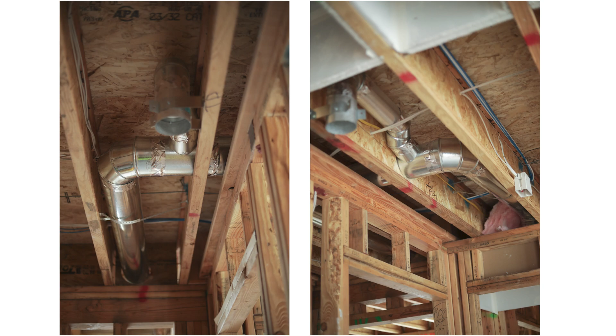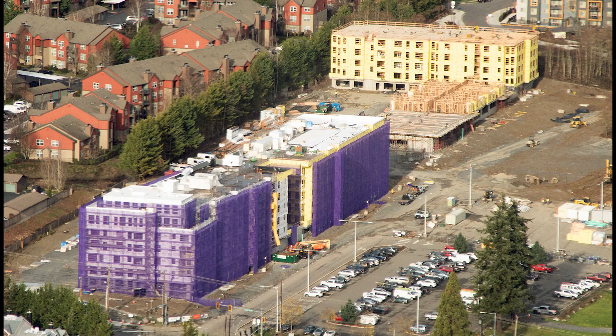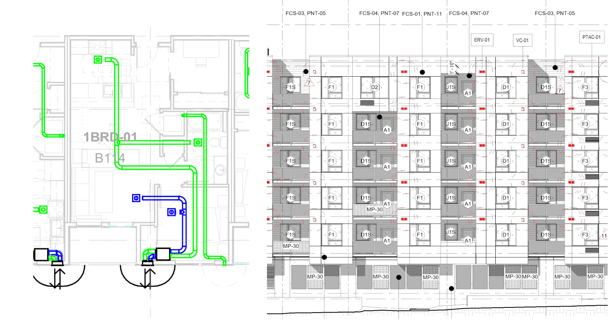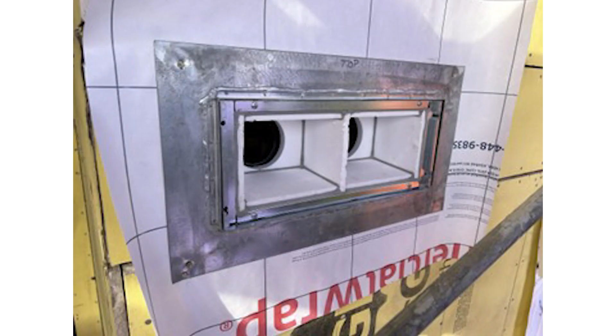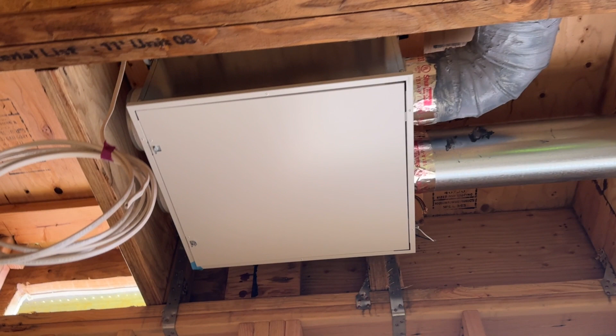Once routing was determined by the structural and mechanical engineers via rigorous coordination, the architect had to verify the clearances required by code for the ERV inlet and outlet were met at the exterior of the building. A new combination ERV exhaust termination and intake on the market was used, helping alleviate some of the overlap. The ERV unit was located as close to the exterior wall as possible, which helped reduce structural conflicts.